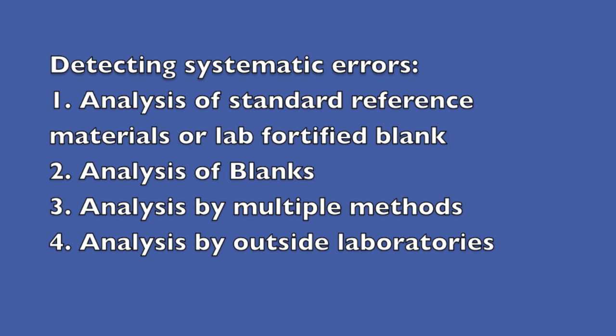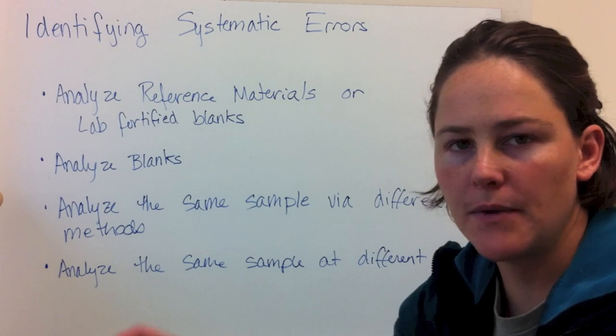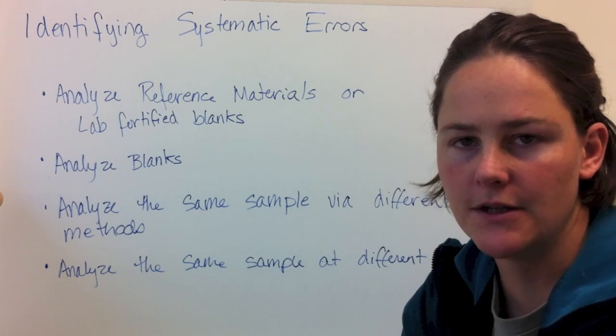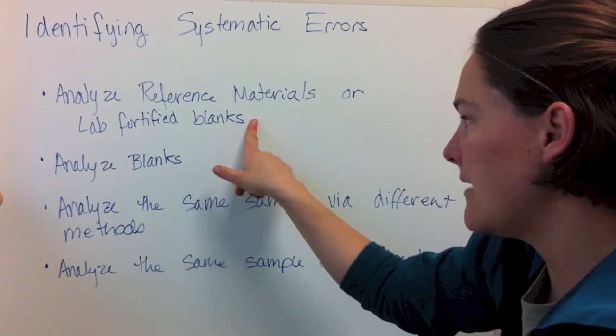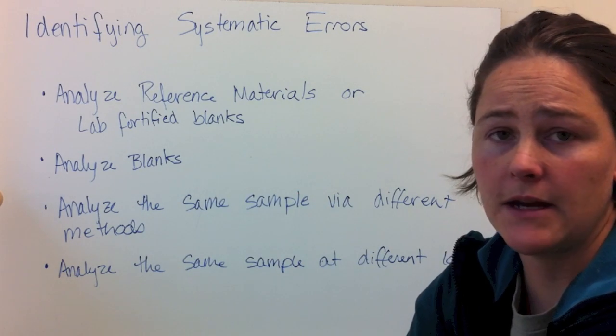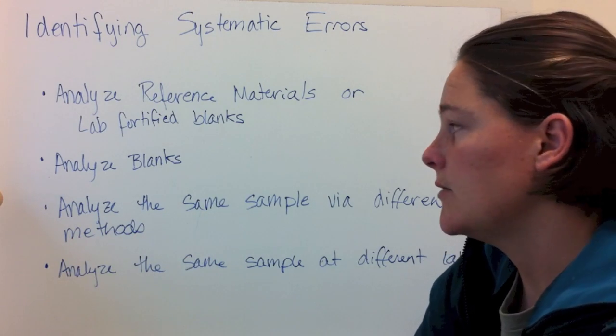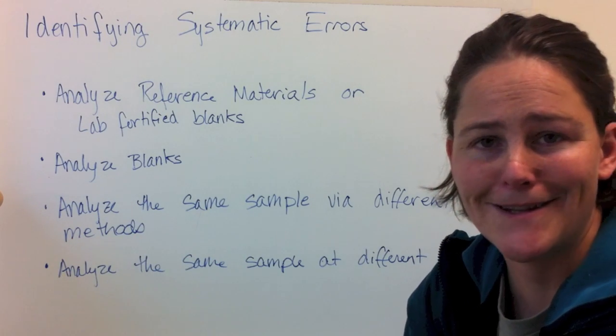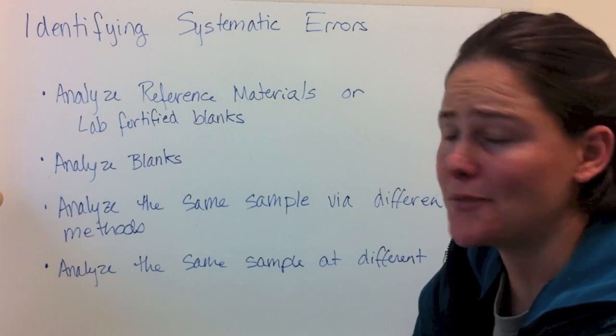All right. So you can analyze reference materials or if you have a sample, you can make up something very similar to your sample in the same type of matrix and then run that. Let's call it a lab fortified blank. You can analyze blanks. That might help you know if your whole baseline is shifted. If your blank is reading something other than zero, then you often will have a problem.